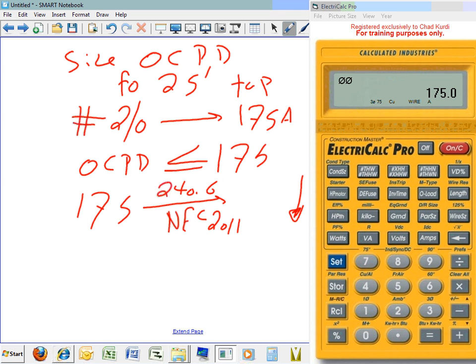If it's not a standard, what do you need to do? Down. I believe it's standard, right? Typical 175, 150, 175. So we hit the jackpot here. Isn't the device giving us the standard? The device: 167 amps, got the wire size, and it told us 175.